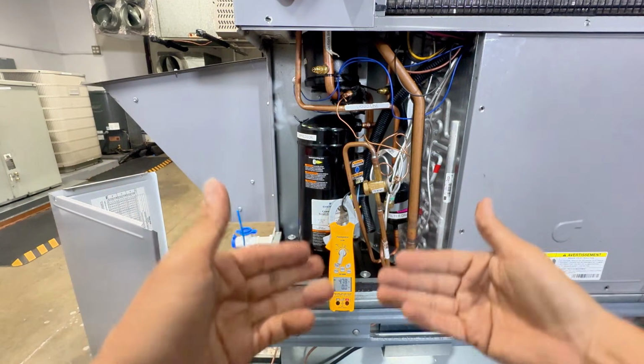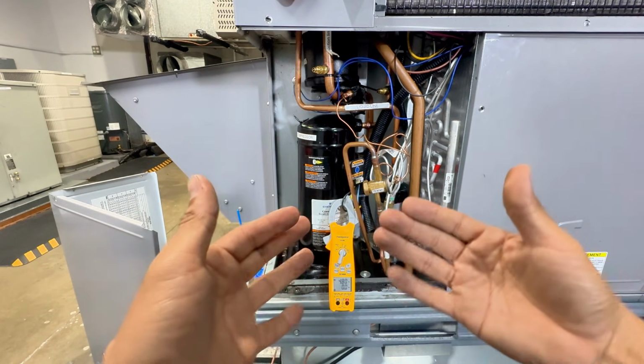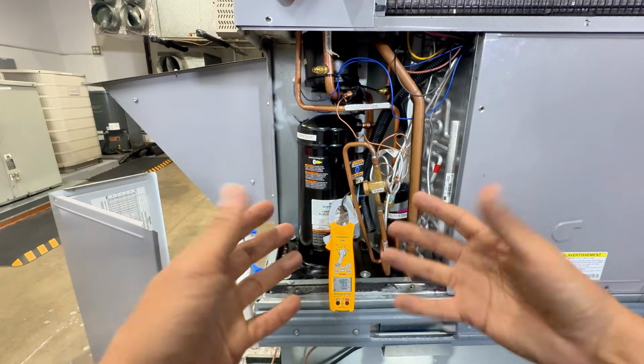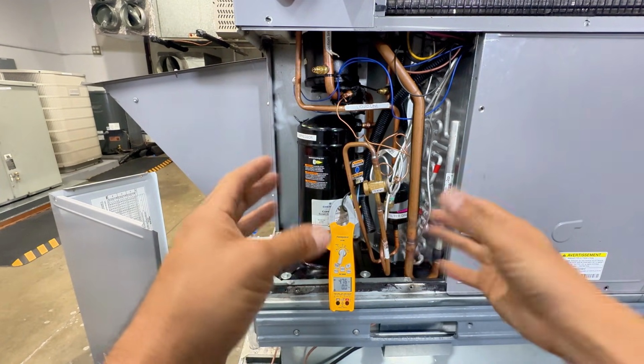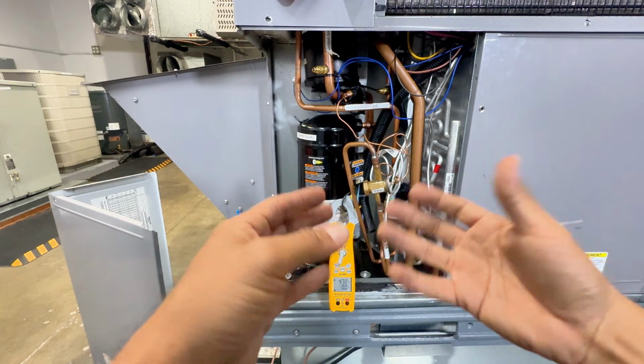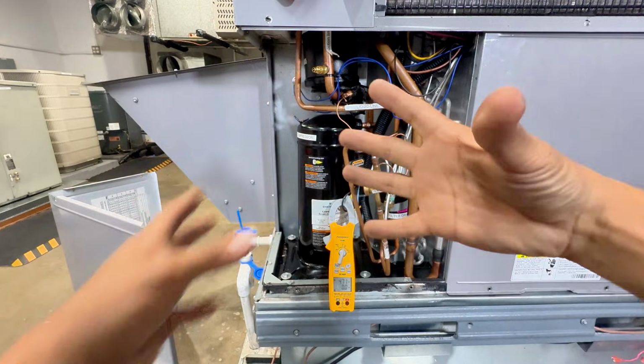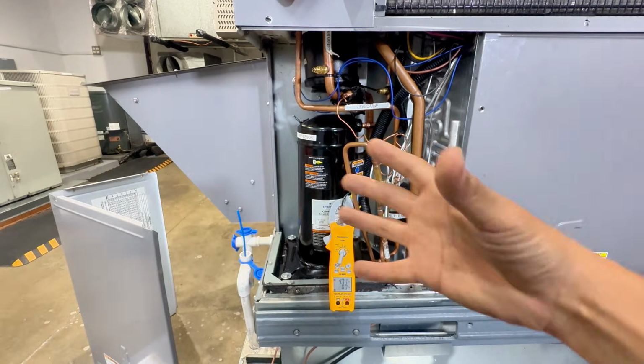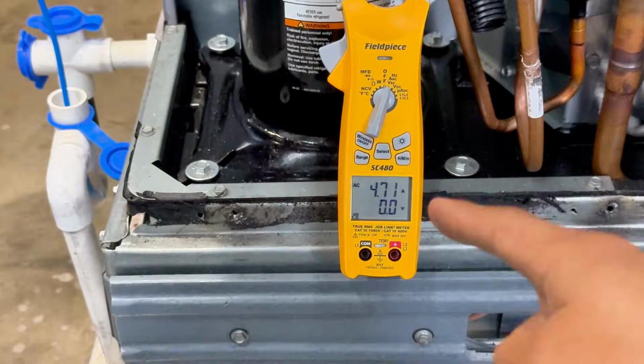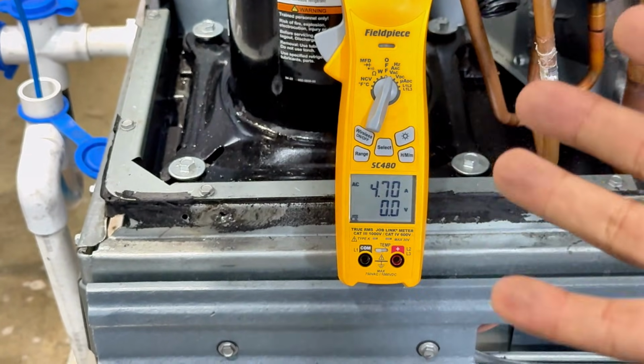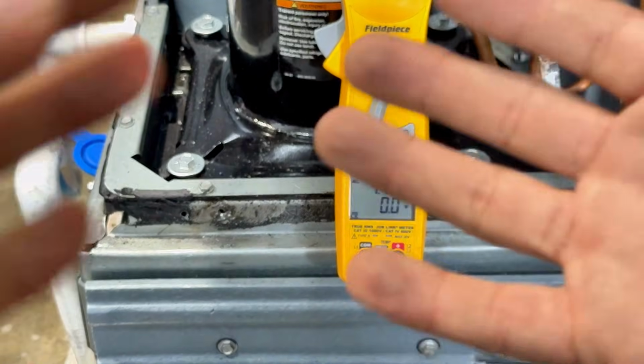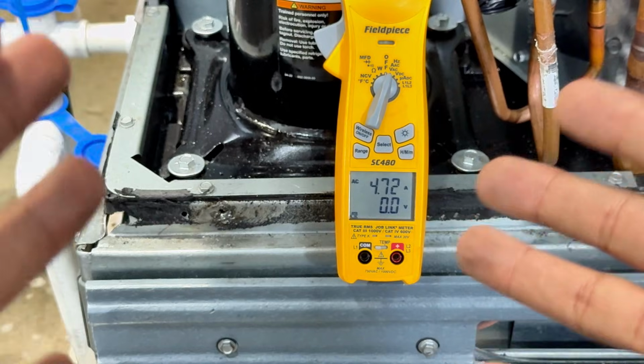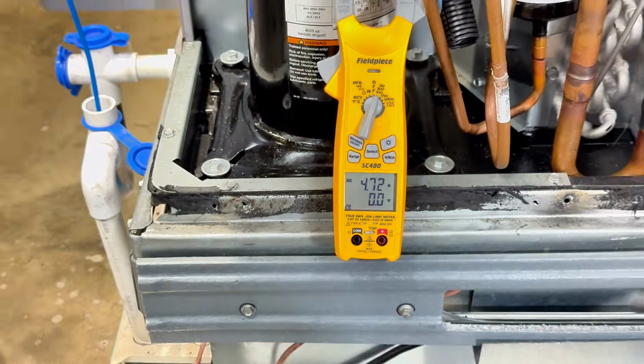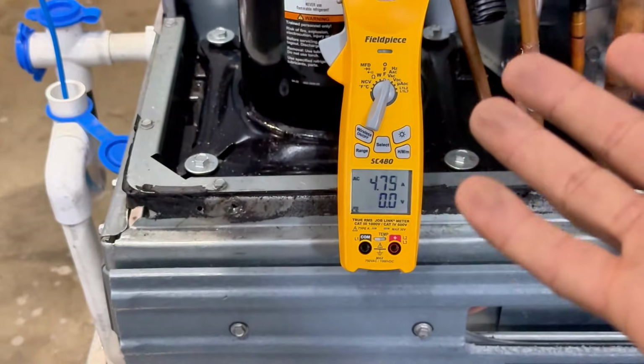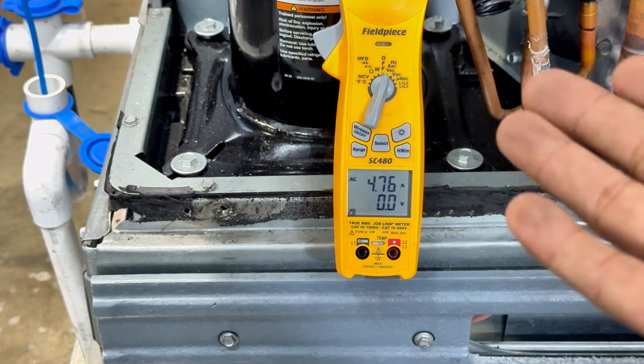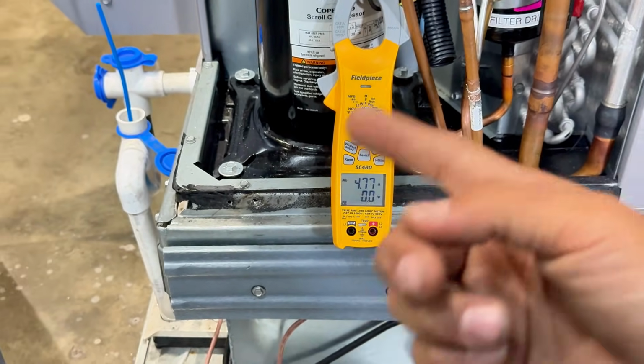Look at the surroundings, at least right now in the lab where I'm at. It's kind of cold right now. You call for cooling when it's hot. So even if it's properly charged and you're calling for cooling on a cold day, it's not under load. The compressor needs heat so that it can do its thing with the refrigeration cycle. But if it's cold, it's going to throw it off, and you're going to think, oh, it's low on charge because it's low amps. No, it's just not under load. So right now it's pulling 4.7, and it's working. It could be undercharged, and if it was overcharged, it would be pulling more than 14.